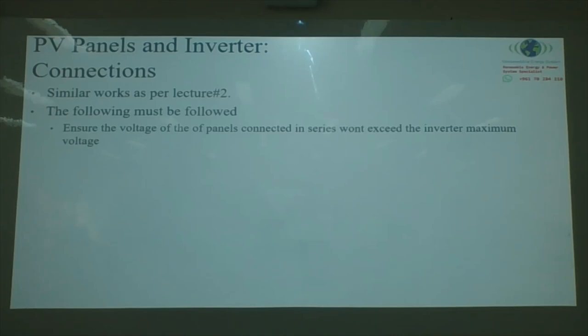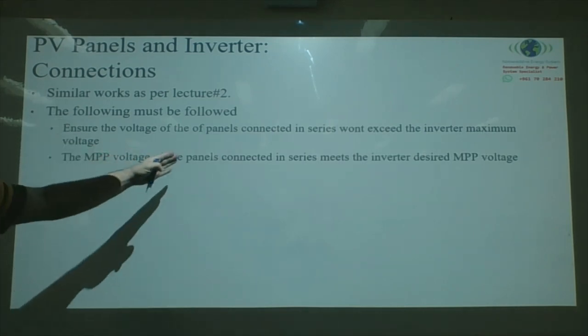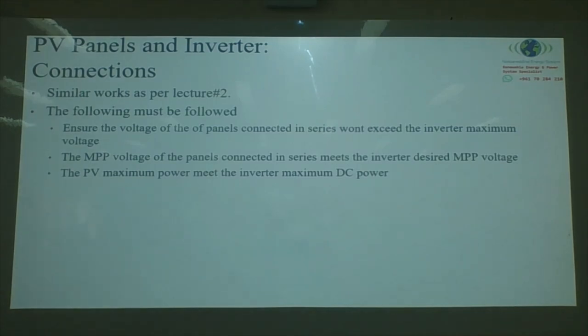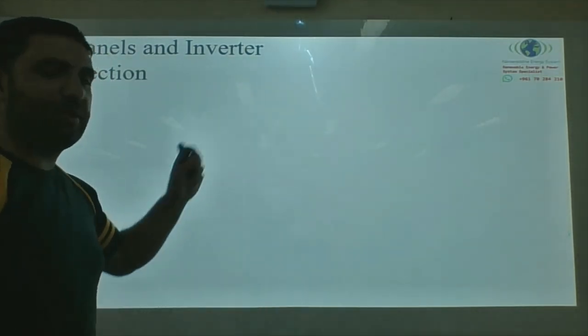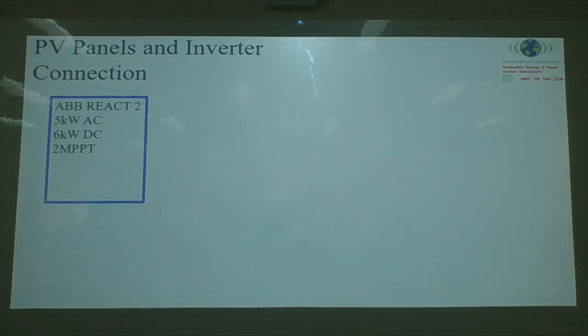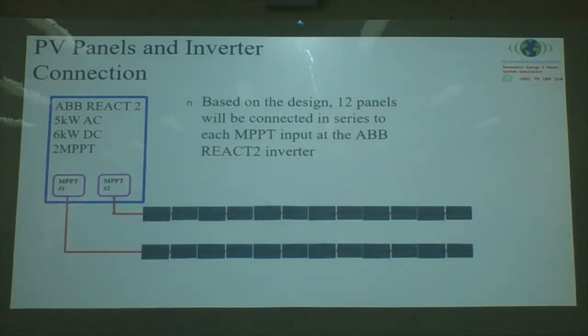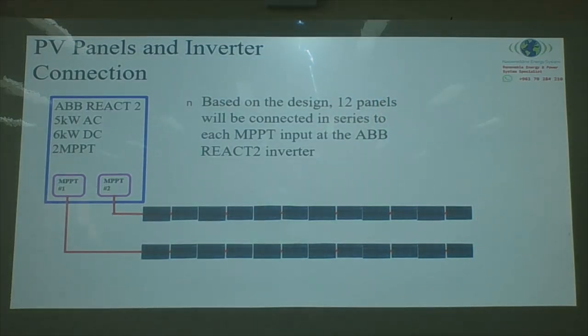For panel connections, as covered in lecture two: the voltage of panels connected in series must not exceed the inverter's maximum voltage; the MPP voltage of panels in series must meet the inverter's desired operating range; the PV maximum power must meet the inverter's maximum DC power; and the PV current must meet the inverter's maximum current. For example, on an ABB React 2 system (5 kW AC, 6 kW DC, dual MPPT), 12 panels would be connected in series to each MPPT input.